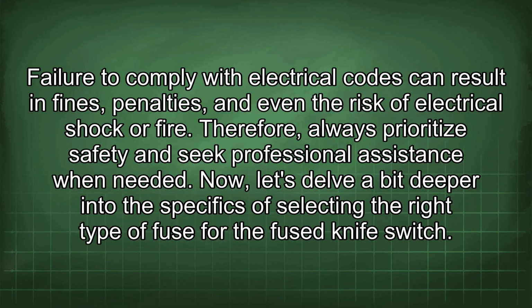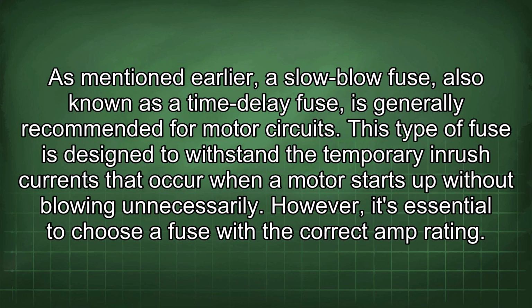Now, let's delve a bit deeper into the specifics of selecting the right type of fuse for the fused knife switch. As mentioned earlier, a slow-blow fuse, also known as a time delay fuse, is generally recommended for motor circuits. This type of fuse is designed to withstand the temporary inrush currents that occur when a motor starts up without blowing unnecessarily. However, it's essential to choose a fuse with the correct amp rating.